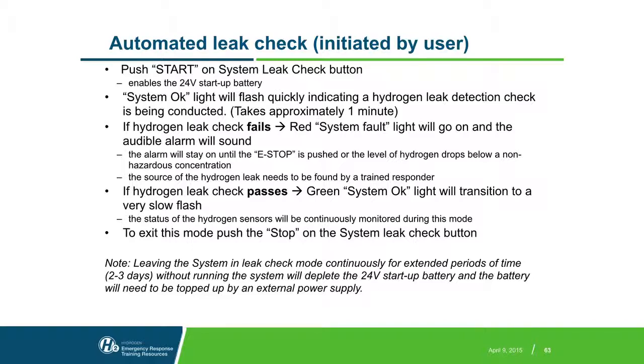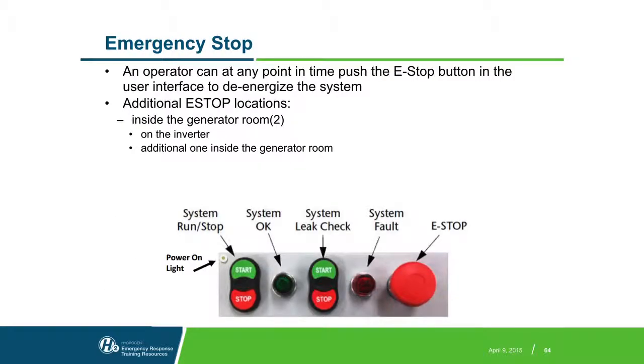Okay. If the user tries to just reset everything and start over, the same thing happens. It's basically not going to start up if it finds that there's a leak. Probably the more likely situation is that it passes, and that green system OK light will then go to a slow flash, and the status of the hydrogen sensors will be continuously monitored during this mode. So they need to stop this by pushing the stop button. Again, they need to stop this action, otherwise that 24-volt system stays powered on. At any point, the e-stop can be hit, and that will completely power down the system.